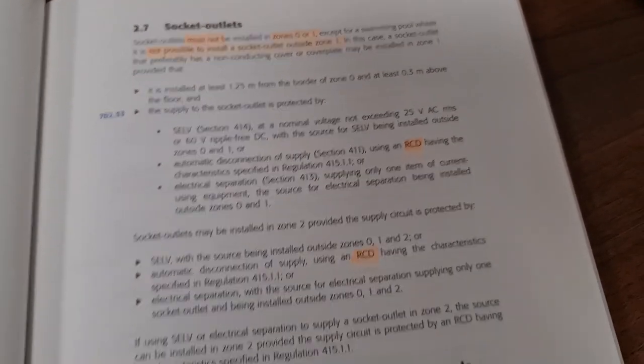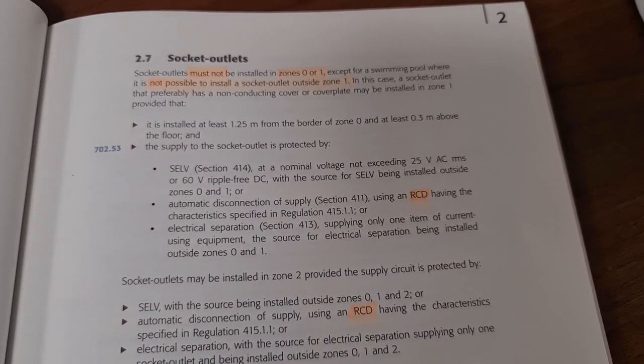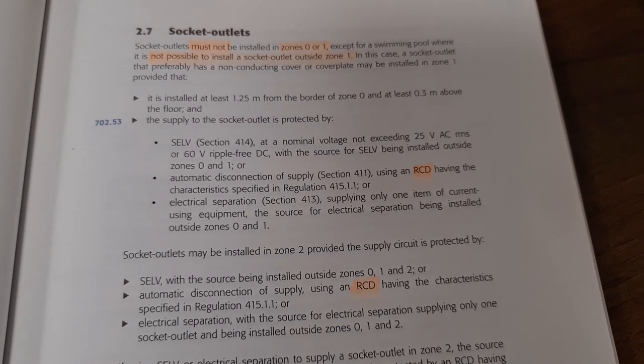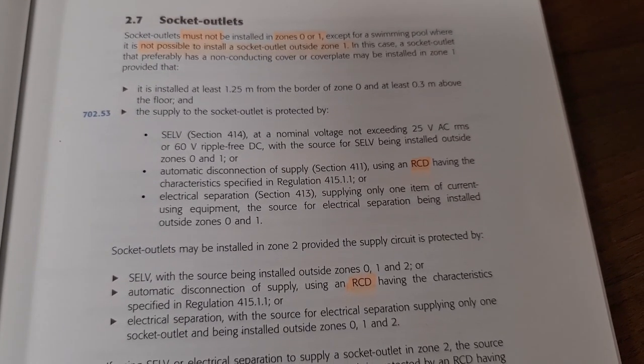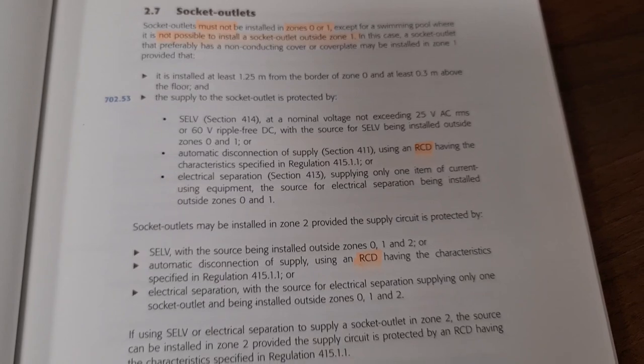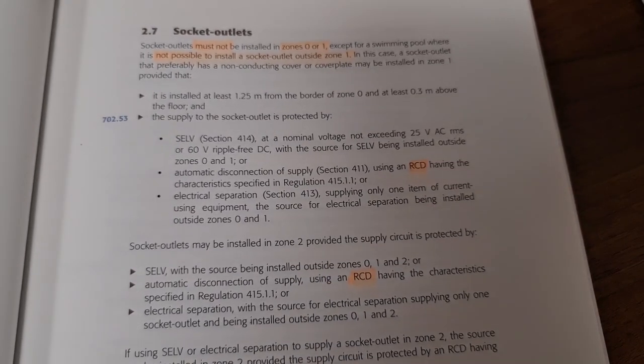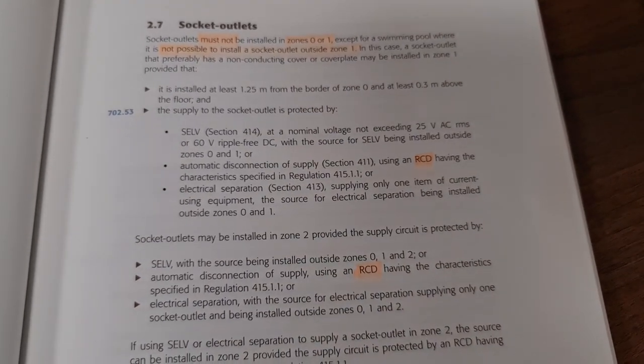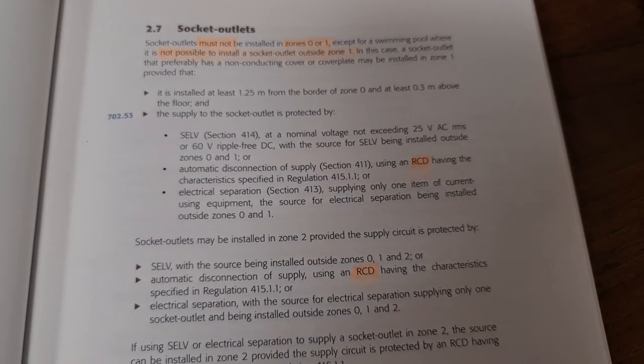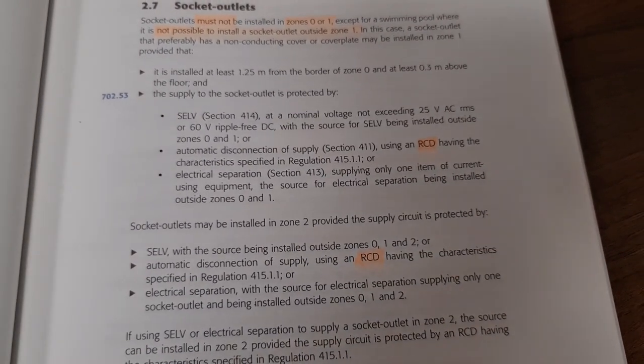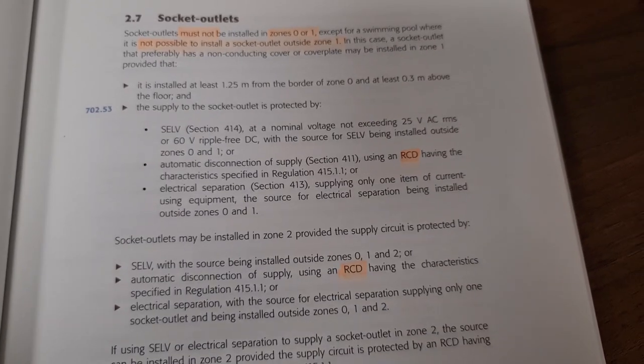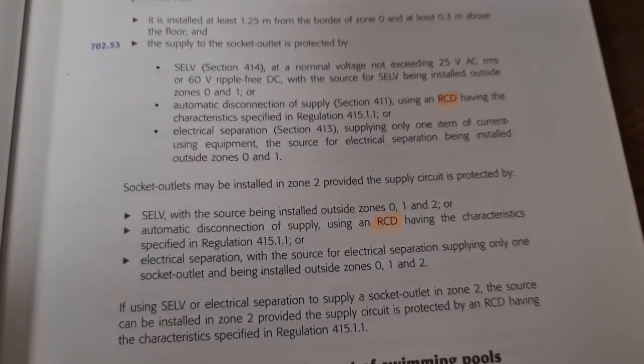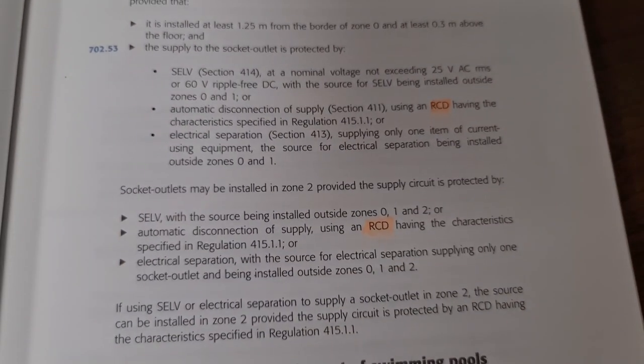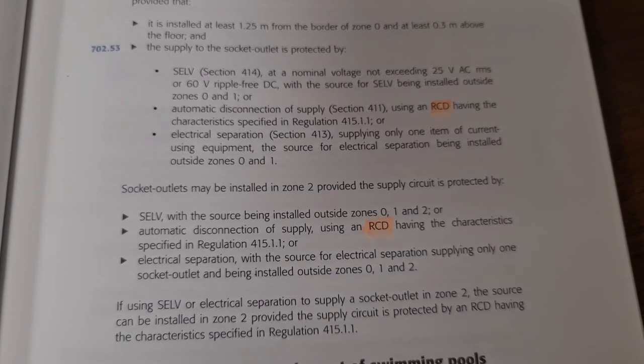Speaking about socket outlets, I wanted to reference this because of inflatable hot tubs. Sockets must not be installed in zone 0 or 1, within 2 meters of the edge of the pool. A lot of the supply cords on those products aren't very long, so you'd have to have the socket within that position. It is allowable, but you need to do certain things, basically putting an RCD on there that complies with regulation 415.1.1.